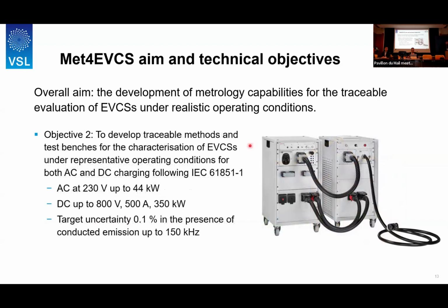The second objective is to develop traceable methods and test benches for the characterization of EV charging systems under these operating conditions that we just measured in the previous objective. And as you can see here, that means AC up to 44 kilowatt, but DC up to 350 kilowatt. And in particular for the DC charging systems, we expect to see more distortions because these are basically rectifier and inverter based devices, so they can inject a lot of distortions into the grid. These are laboratory measurements, so we aim for a target uncertainty of 0.1% under real world conditions.